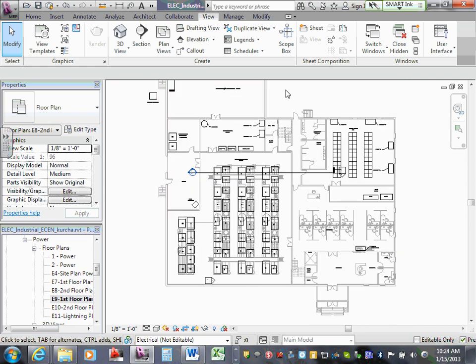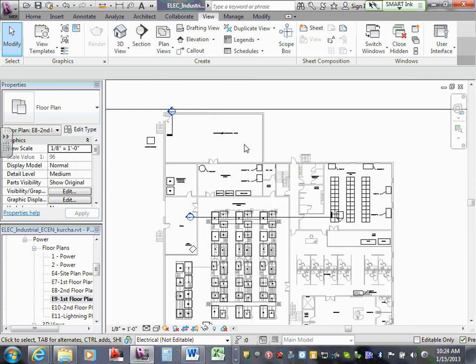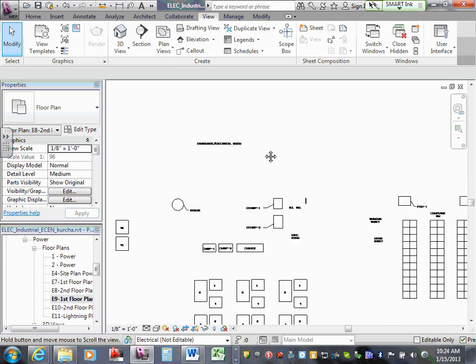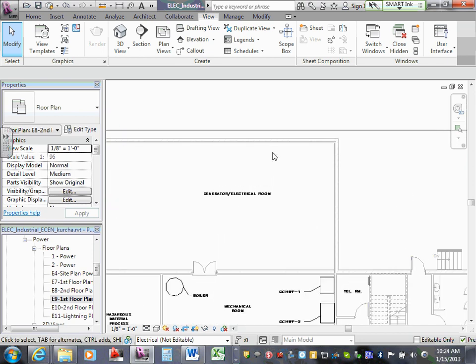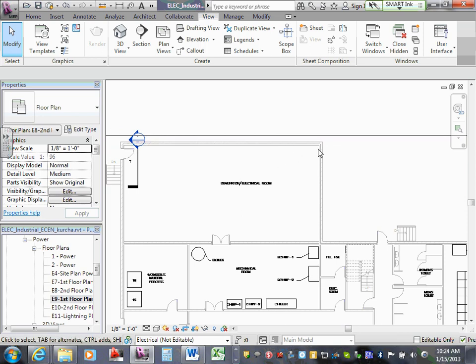So we're going to be monitoring the 4 sprinkler zones. So up in this area, you have 4 sprinkler zones. You're gonna have your main flow and your main tamper, and you're gonna have usually a flow per zone. So you're gonna be looking at what they have is 4. You put 4 dual monitor modules up in this area.